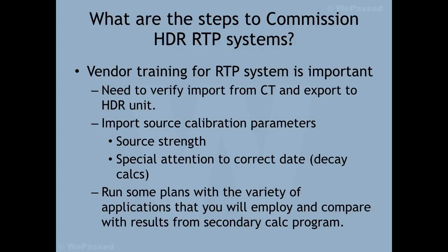You need to test the CT image with your planning system, so you scan a phantom, or some special phantom, and examine the geometry and the volume. You test that from your treatment planning system and compare it with your CT data.